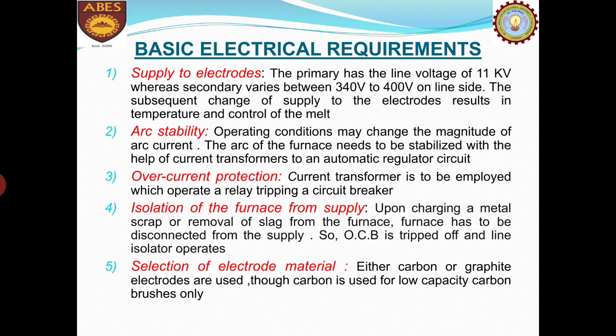The electrodes which we generally use in an arc type of furnace are either carbon type or graphite. Now the latter is the refined and specially treated form of carbon and has 4 times the conductivity. The carbon electrodes on the other hand are cheap and have a current density of approximately 8 to 15 ampere per centimeter square, whereas the current density of graphite is approximately in the range of 32 to 60 ampere per centimeter square. Now thus we can say by looking at the current rating that carbon is suitable for low capacity arc furnaces only.